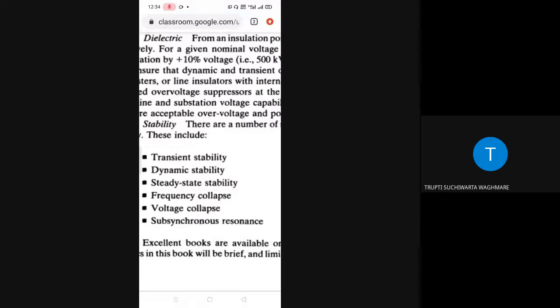The frequency droops suddenly, and the under frequency relays, as protective devices in the operation of that grid, operate sequentially. Because of that, the loads get disconnected and the whole region becomes blackout. So that is the frequency collapse, basically an example of frequency collapse.